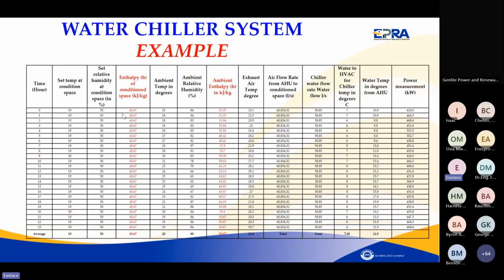As I said, when you are calculating the heat required to be removed between the ambient conditions and the controlled conditions, use the enthalpies, not the changes in temperature, because there is both latent and sensible cooling or heating. The other thing you have to measure is the exhaust temperature of the air leaving the room. Then you need to measure the airflow. You need to measure the water flow. You need to measure the temperature of water going to the HVAC AHU unit, both going in and coming out. Then you measure the power consumption of the compressors or of the chiller system.